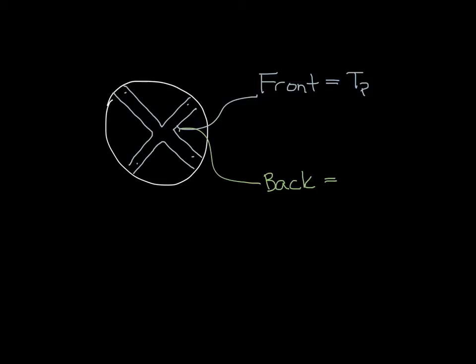So remember that the total pressure is the static pressure plus the velocity pressure. A flow sensor is taking a total pressure reading on the front of the sensor where it sees both velocity and static pressure. And then on the back side where there's no velocity and therefore no velocity pressure, it is taking a static pressure reading. So now if you know the total pressure and the static pressure, you can calculate velocity pressure, which you use to calculate velocity, which you use to calculate CFM.